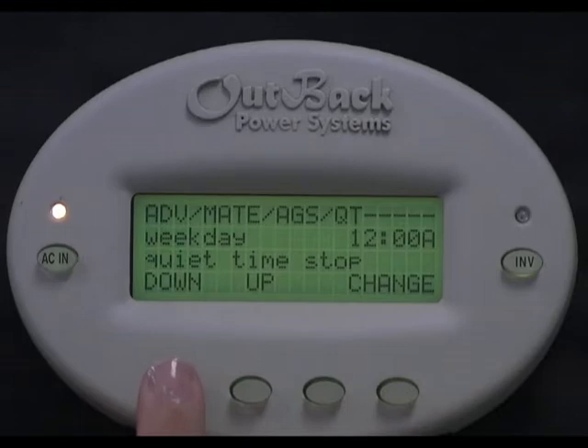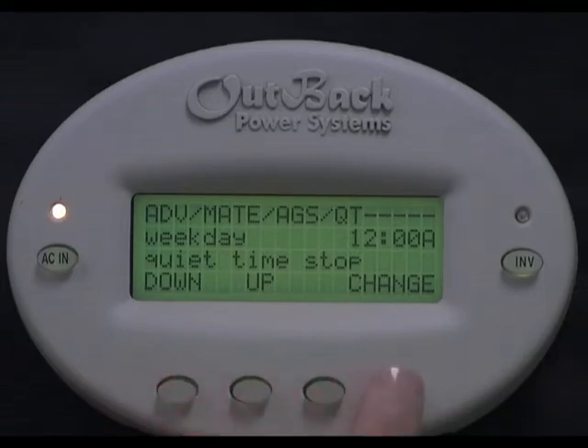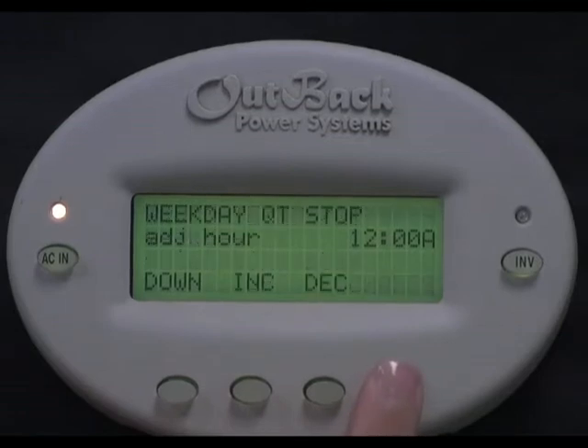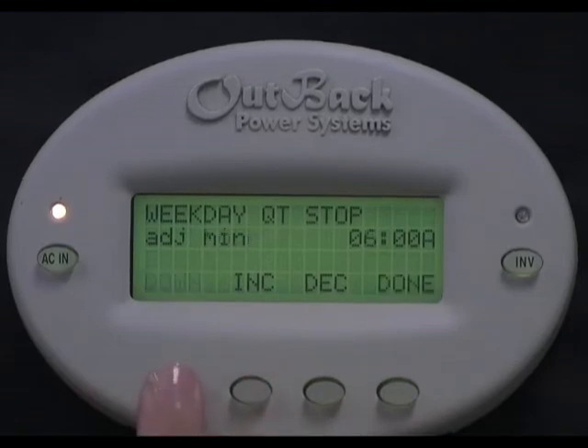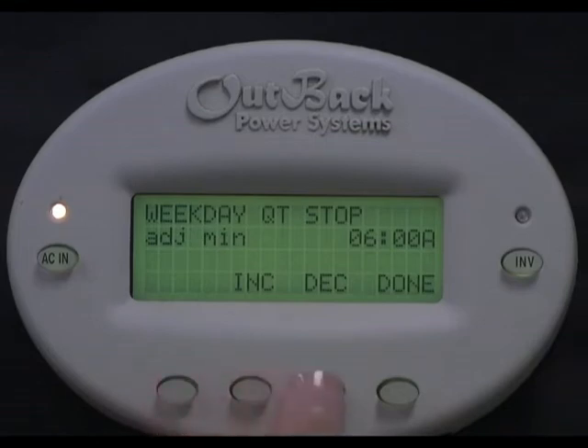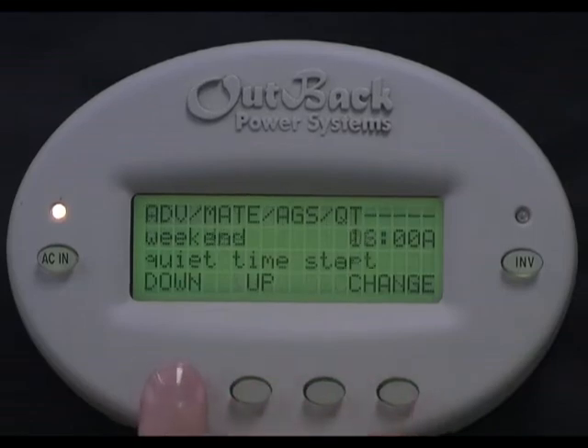Weekday Quiet Time Stop is the stop of the time period when you don't want the generator to run Monday through Friday. So in our 10pm to 6am example, this time would be set for 6am. To set it, select Change, then Increase or Decrease to adjust the hour. Select Down, then Increase or Decrease to adjust the minutes. Select Done, then select Down.